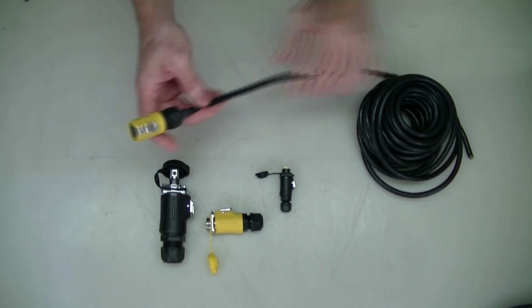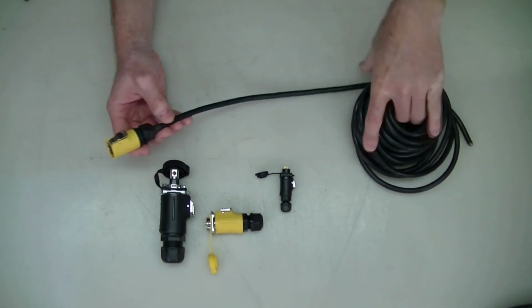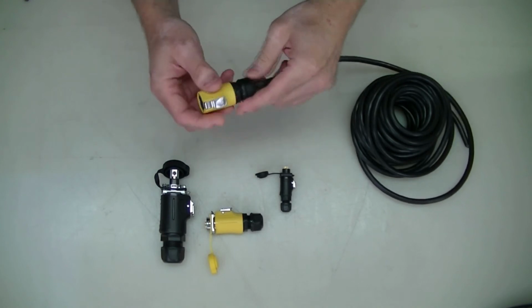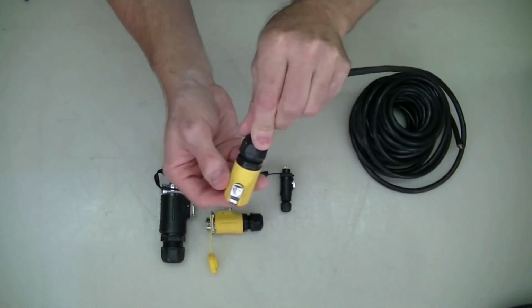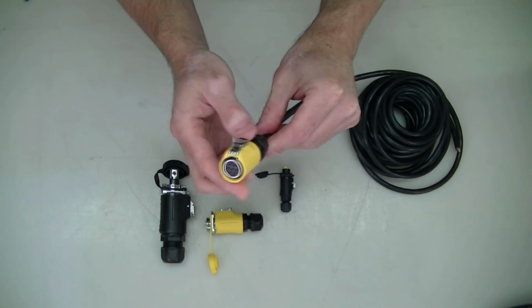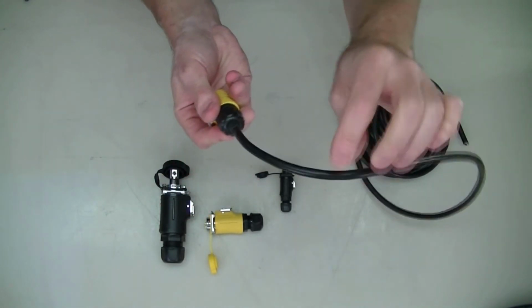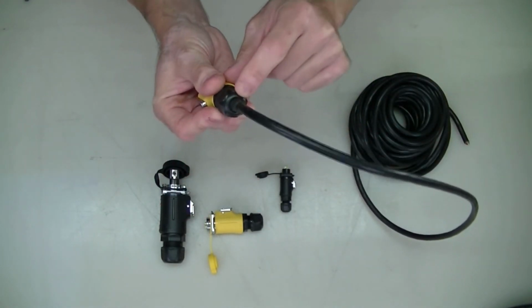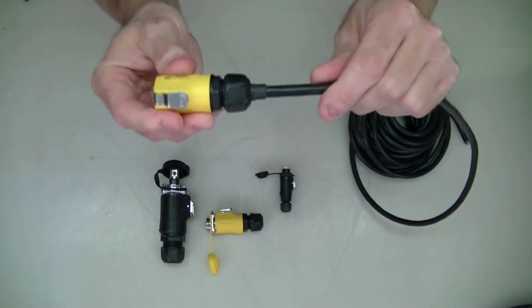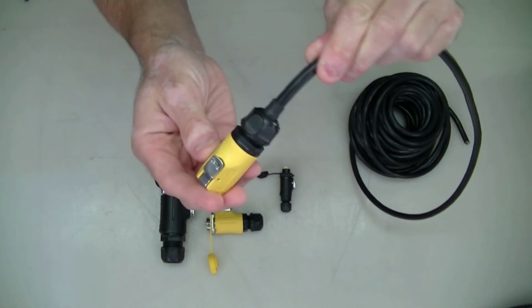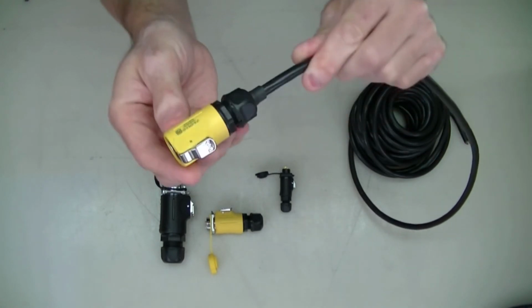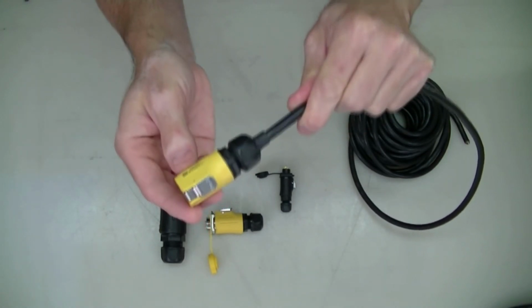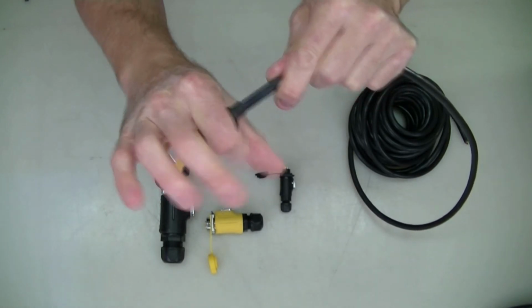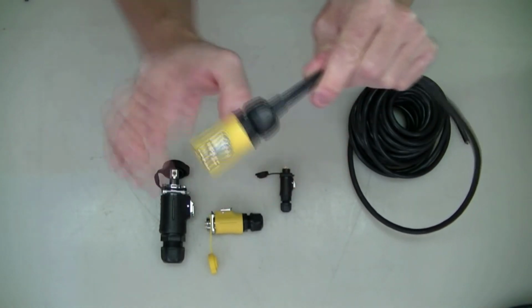This cable right here is an 18 gauge 6 conductor cable, which is just about right for the pins inside the connector. But the cable jacket is too small for the cable gland, so I've had to build it up with a couple layers of adhesive lined heat shrink to keep it round and increase the diameter to the point where the cable gland can actually seal around it and be watertight.